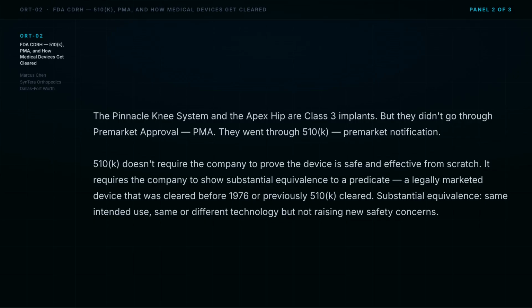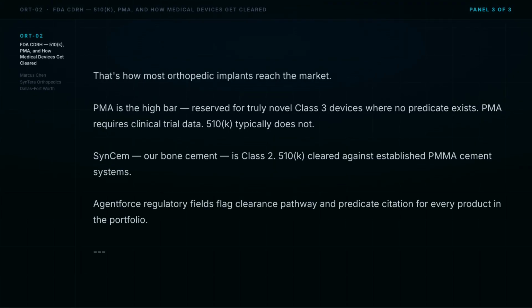510K doesn't require the company to prove the device is safe and effective from scratch. It requires the company to show substantial equivalence to a predicate, a legally marketed device that was cleared before 1976 or previously 510K cleared. Substantial equivalence: same intended use, same or different technology, but not raising new safety concerns. That's how most orthopedic implants reach the market.